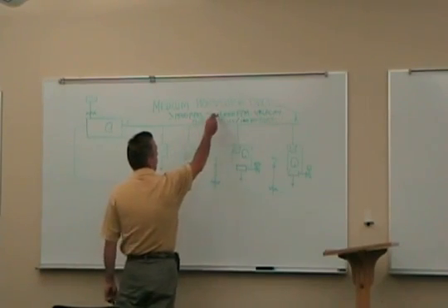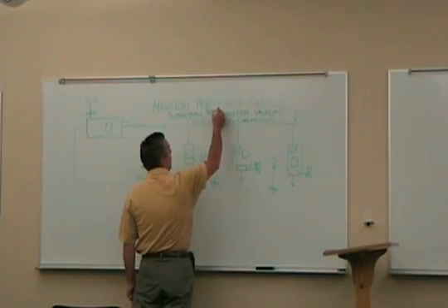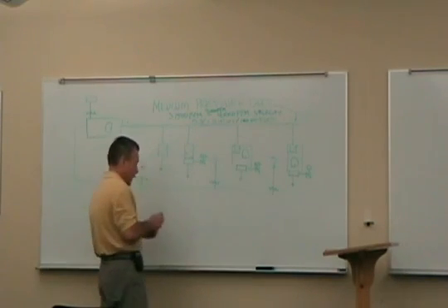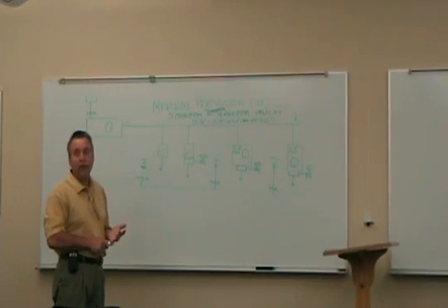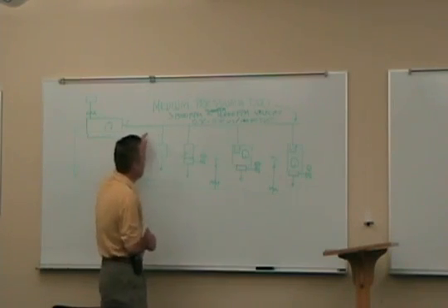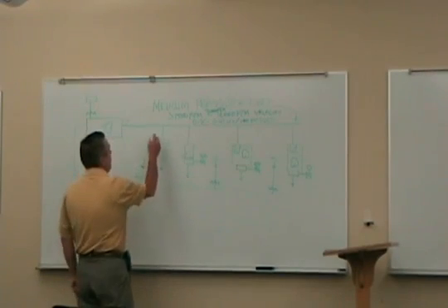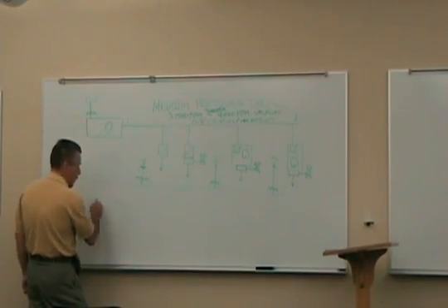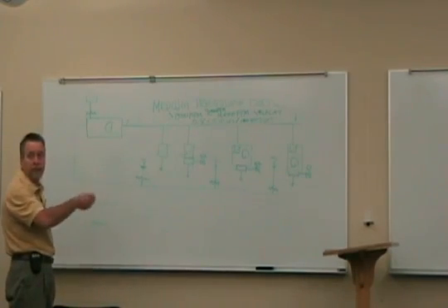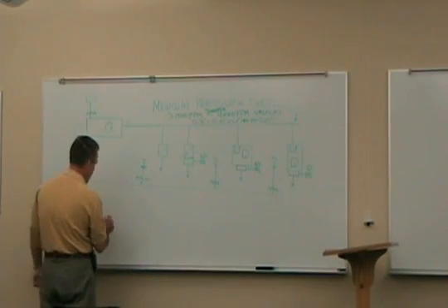So you'll see a lot of duct that size generally around the 3,000 feet per minute. That's pretty fast. It's pretty high velocities. High velocities cause high pressure drops. But you've got to fit it into space. You've got to fit it above the ceiling. So what you'll see in these types of fittings, and generally this is the spiral duct that you buy pre-manufactured, or you can build it.